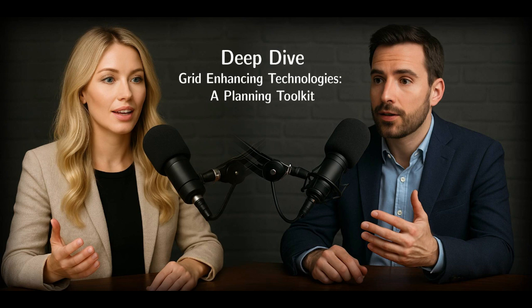High temperature, low sag, HTLS conductors. All right, next up, advanced conductors, specifically high temperature, low sag, or HTLS conductors. This comes into play when existing lines actually need replacement or reconductoring. Okay, so this is about upgrading the wire itself. You're not just replacing like for like, you're putting in something much better. Exactly. It offers a significant capacity increase, often using the existing towers and structures. That's a huge advantage, avoiding new rights-of-way. Yeah. What are the main technology options for HTLS?